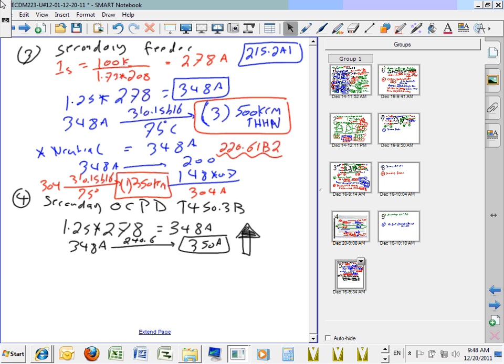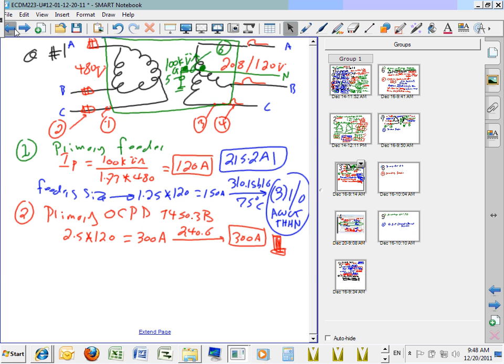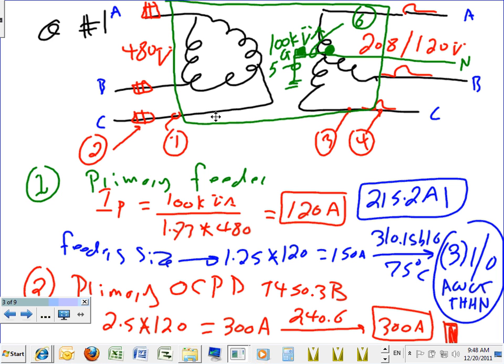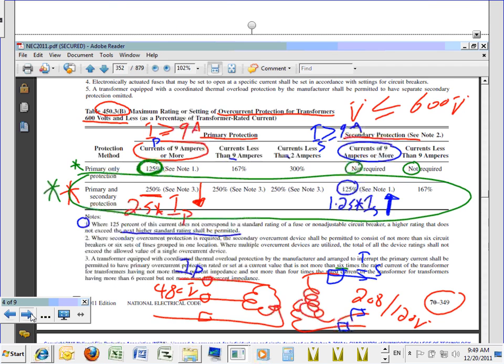The example that we did is typical for any low voltage transformer like the one that you're looking at. Typical. So I don't need to give you 3-4 more examples like this. All you have to do now is change the kVA here into 500 kVA, 1000 kVA, and do the math again. Same calculation. What I'm going to change this time, if you look at the voltage, both of them are less than 600 volt. I need to put one example where the voltage on the primary is different, because its calculation is going to be slightly different. So here's the second example.